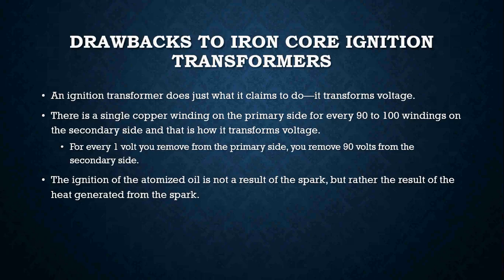Now, one of the drawbacks to iron core ignition transformers is, well, a transformer does exactly what it's supposed to do. It transforms voltage. There is a single copper winding on the primary side for every 90 to 100 windings on the secondary side, and that's how it transforms voltage. So for every 1 volt you remove from the primary side of that transformer, you remove about 90 volts from the secondary side. So the ignition of the atomized oil is not a result of the spark, but rather the result of the heat being generated from the spark.